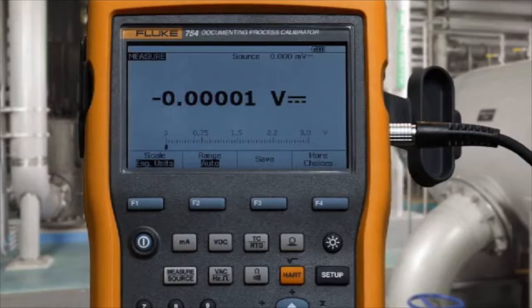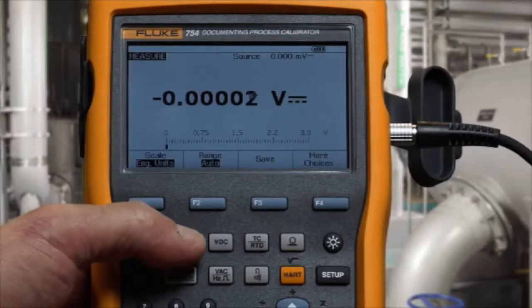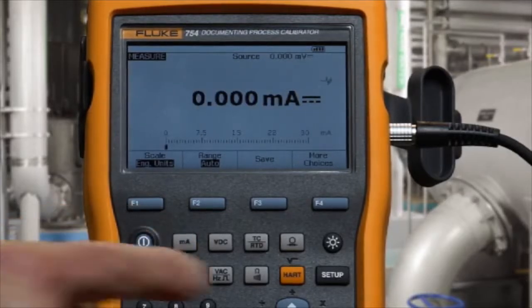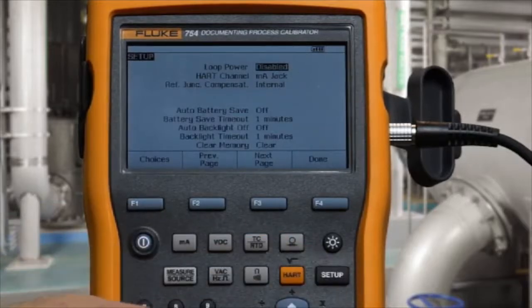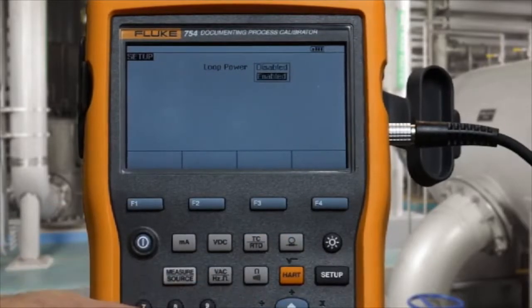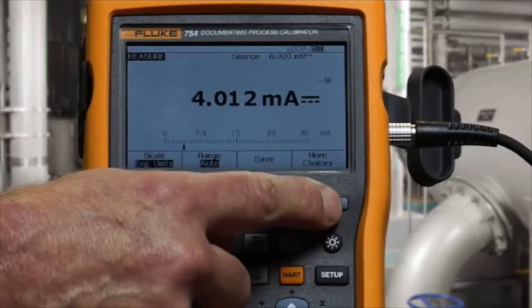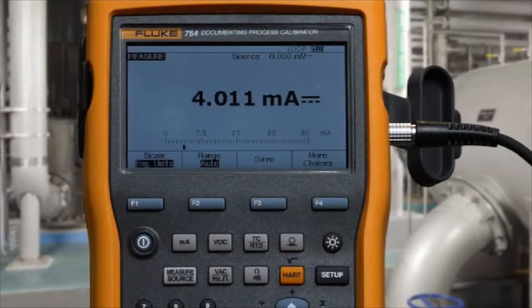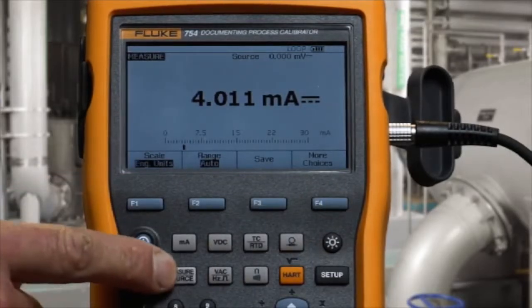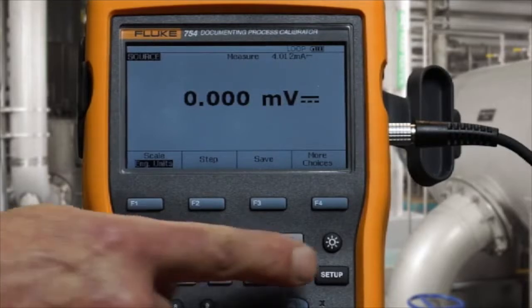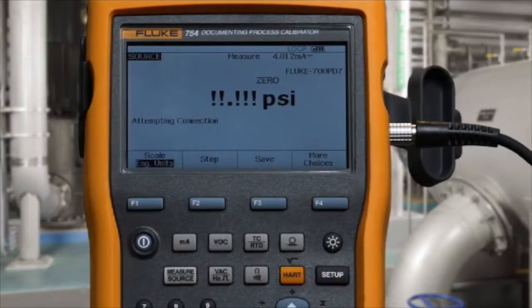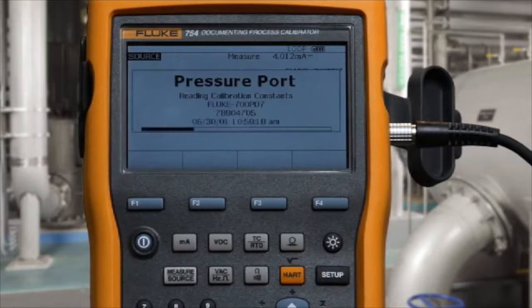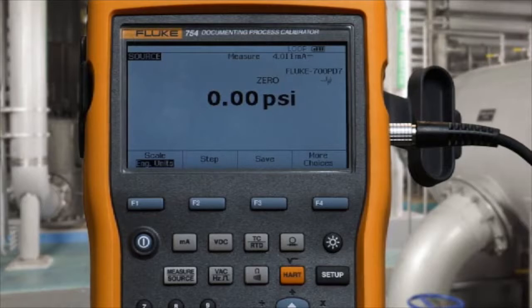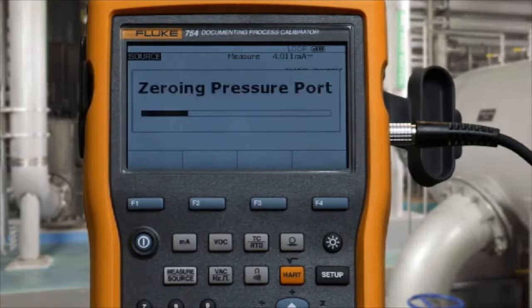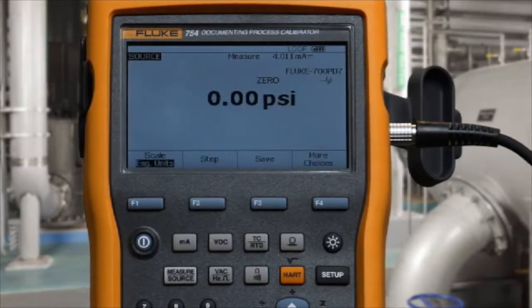To initiate the test, we want to measure milliamps and turn on the loop power. Next step is to configure the source for pressure. Vent to atmosphere and press clear 0 in case there's any electronic offset to clear.